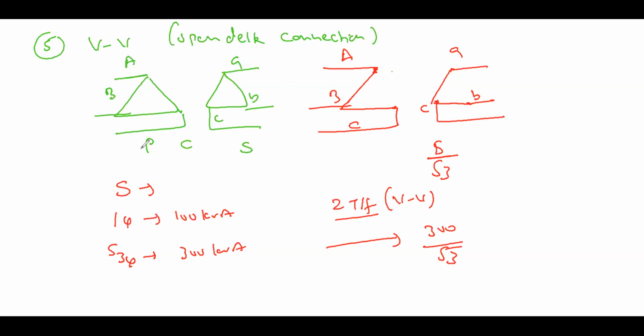You can mention this: 3-phase rating of transformer is 300 kVA. If it is operated in VV connection, its rating is 300 by root 3 kVA.